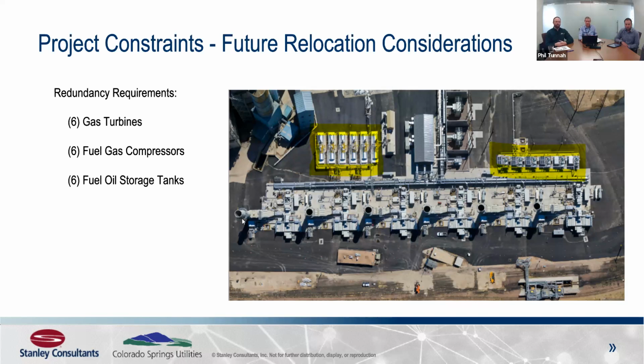When designing the supplementary systems for natural gas, there are 6 gas compressors to bring the gas to the correct pressure for the units, matching the 6 units, sized so that if you take one away, the remaining 5 compressors could still supply the full demand.